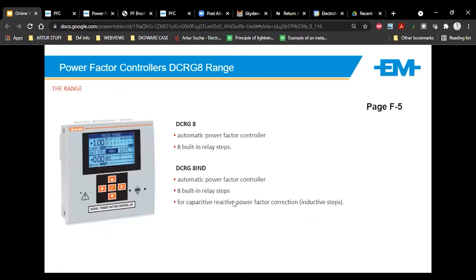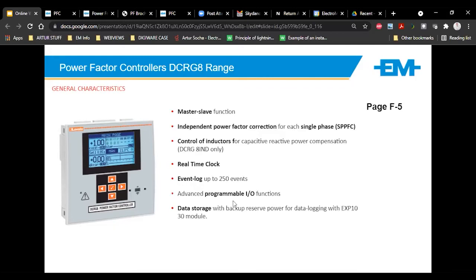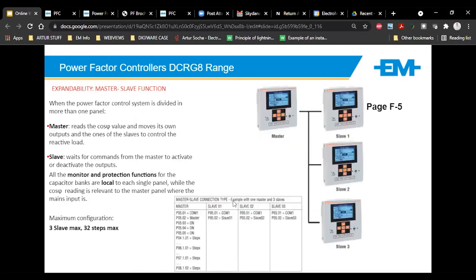Then the controller up from this, and this is the one I like to use, a DCR-G8. This we do on all our floor standing systems, the much bigger systems. It's a lot more advanced. It's got power analysis built in. It's got what we call master slave. So if you ever exceed the amount of output, it's probably the only controller in the market that lets you master slave multiple controllers off one. So we've built cabinets up to 1,600 kVAR. I had to create master slaves just due to the size. That's just an example of what the master slave would look like.